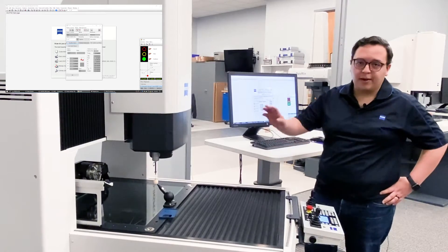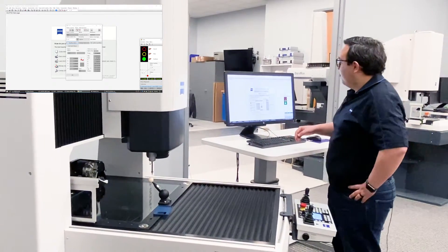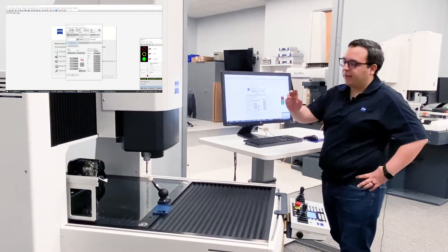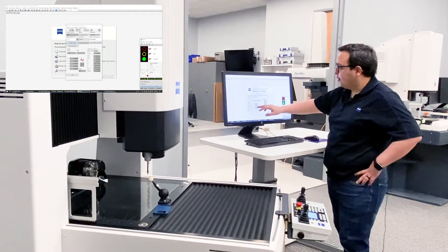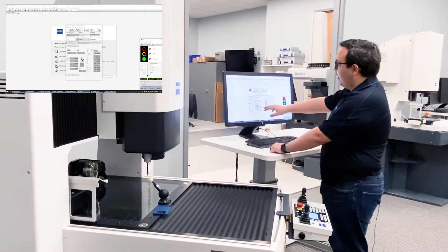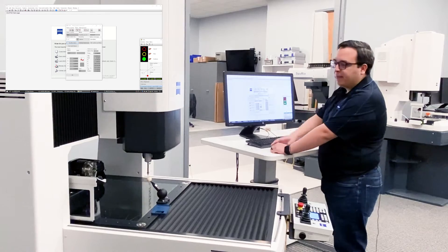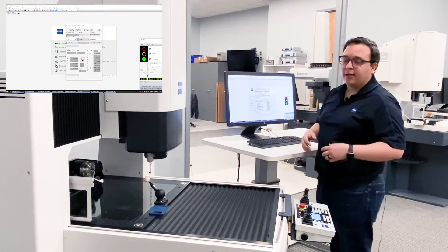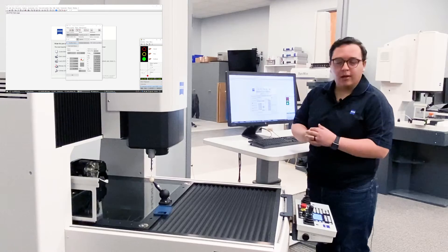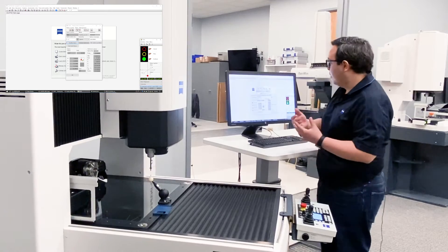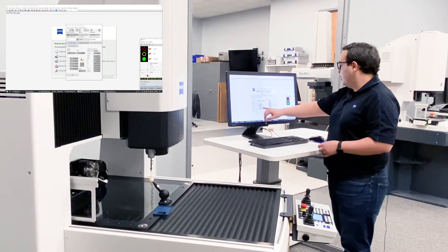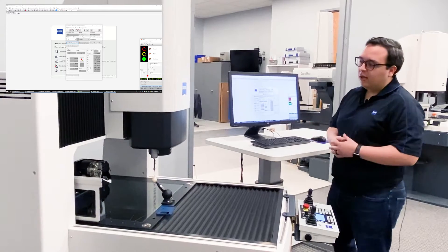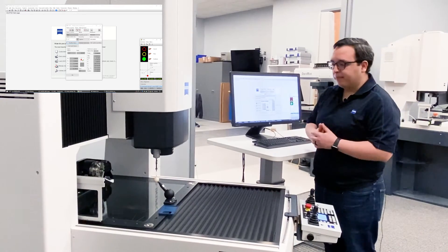Now we're actually finishing up. What we want to look for is the radius — make sure that it makes sense. We're also going to look for this value S — S is for sigma. Effectively what it does is calculate how round the probe is, or how well it was able to measure it. Here we're in metric, so we're two tenths of a micron — so we're actually measuring it really well.